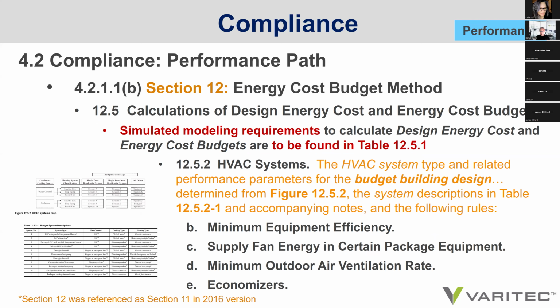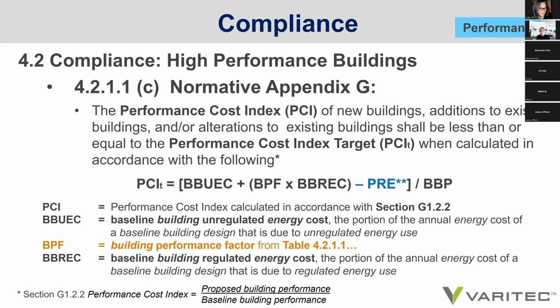It also covers minimum equipment efficiency language, supply fan energy in certain package equipment, minimum outdoor air ventilation rates, and economizers. Normative Appendix G is an appendix that was really designed for high performance buildings, for buildings that want to go above and beyond the minimum prescriptive methods offered by 90.1, in complying perhaps with USGBC's LEED version 5 requirements or LEED version 4. Normative Appendix G gives the criteria to provide an appropriate, valid assessment of what that added energy efficiency is.